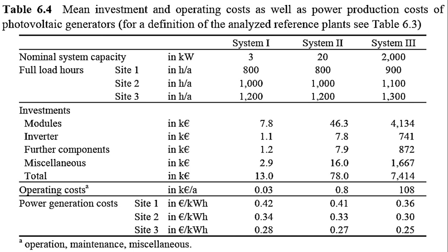The installations such as meter box and the connection to the grid, assuming sufficient experience of the contractor, also cost a minimum of 2% of the overall plant's investment. The operation costs include the maintenance and the servicing cost, as well as the future expenses, for example repairs, module cleaning, meter rent, insurance, etc. According to the installation type and the plant's size, the annual operating costs lie between 5 to 30 euros per kilowatt for the analyzed reference plant expenses that are shown in this table.